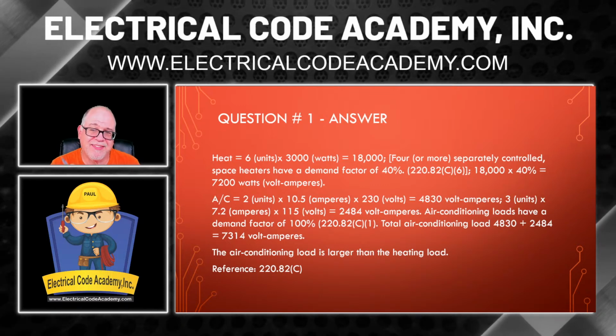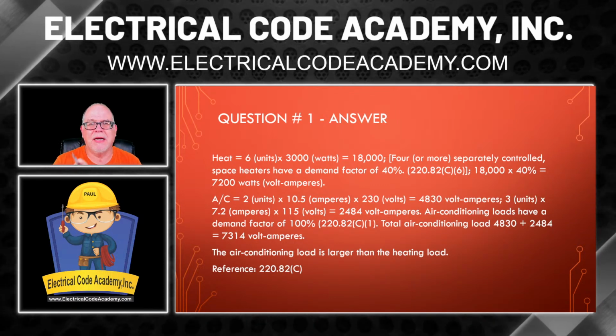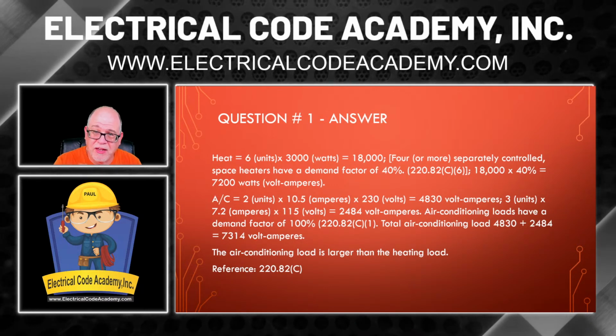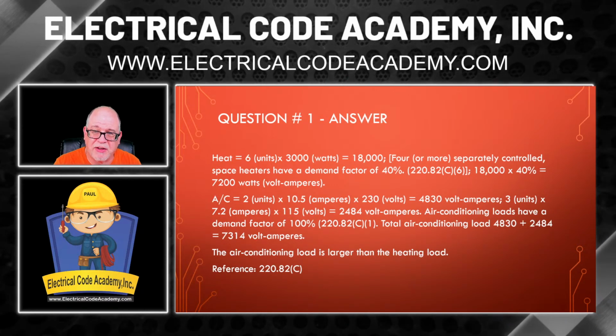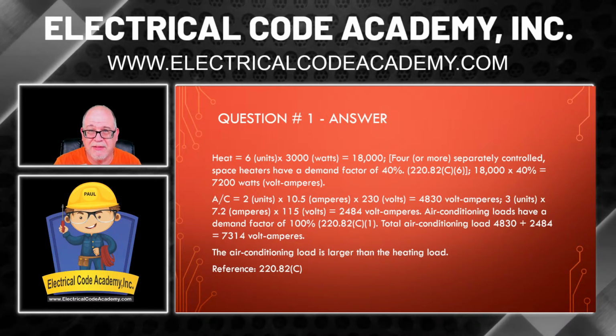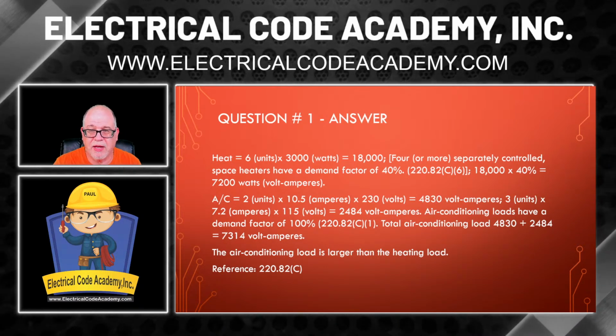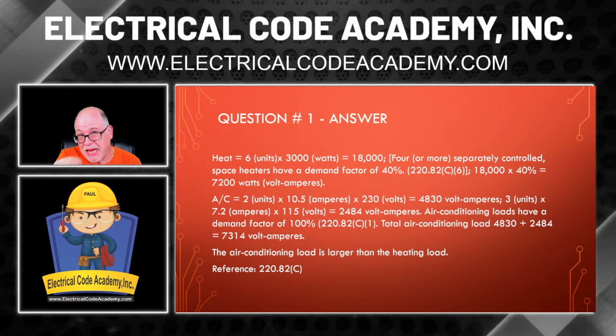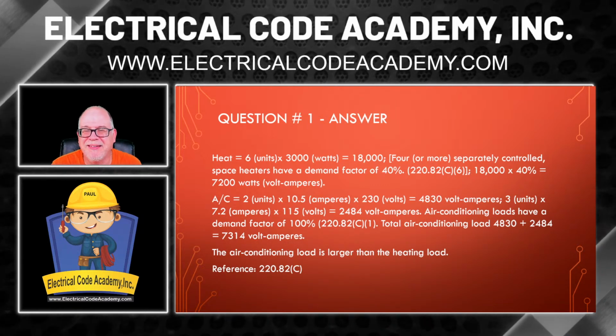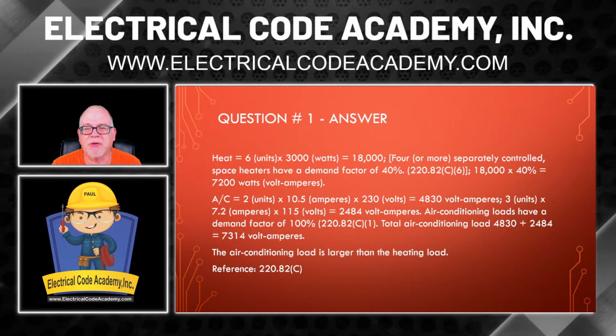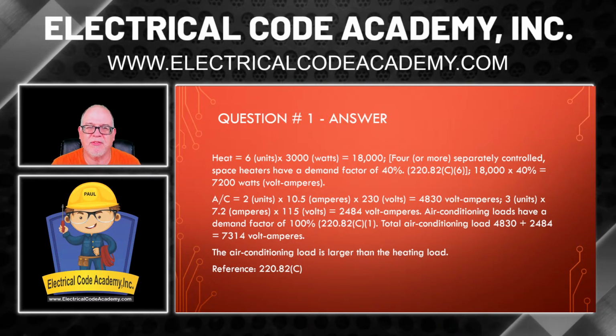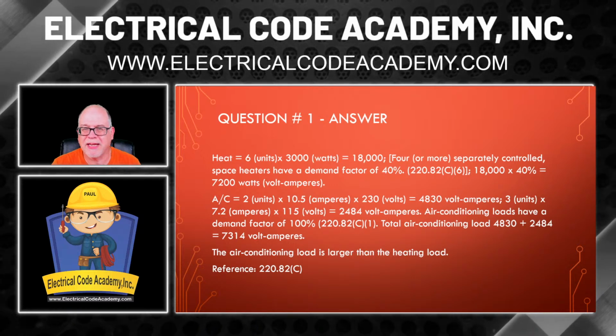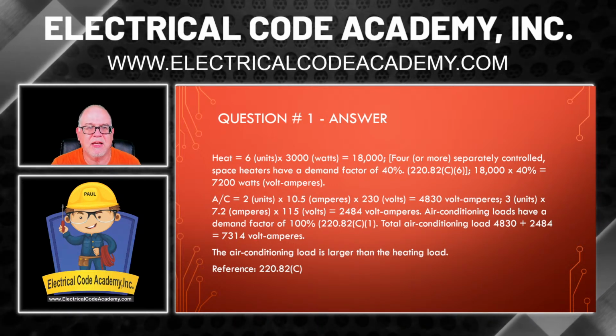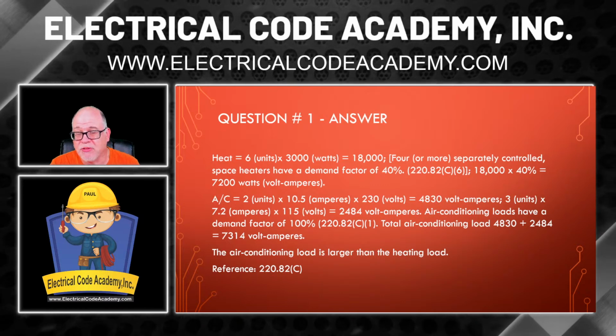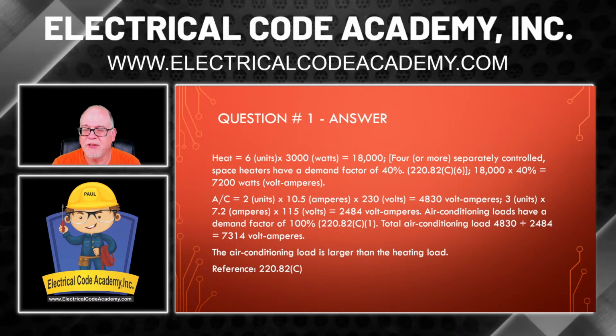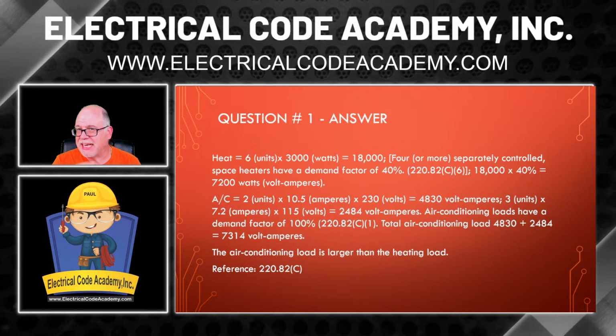Now, remember what it said? It says that we take what? Now, this says 220.82(C)(6), but which one was it actually? It was (5) that we're using for the heat. So, typo. We're doing 18,000 and we're going to multiply that by 40%. That gives us 7.2 kW, or in our case, since we worked it out in watts, it is 7,200 watts, or 7,200 VA. Now let's look at that AC.